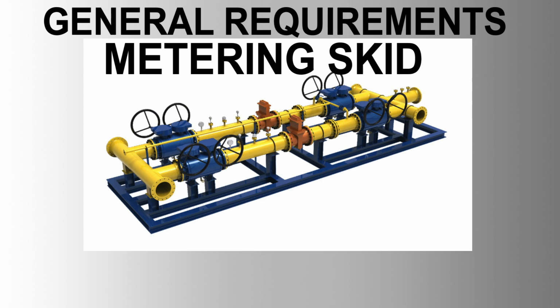Technical data summary. Accuracy. Turbine meters, 0.25% of reading. Ultrasonic meters, 0.15% of reading. Coriolis meters, 0.1% of reading. Output signal, 4 to 20 milliamps with HART communication. Material, stainless steel. Mounting, vibration resistant, environmentally protected, easily accessible.